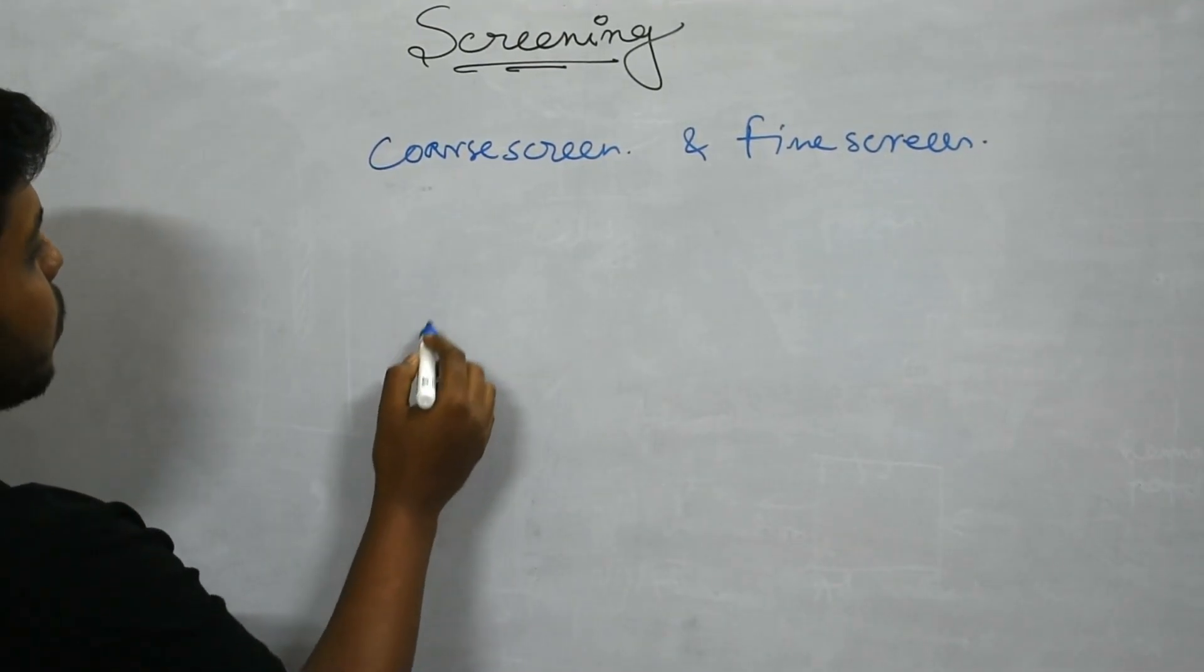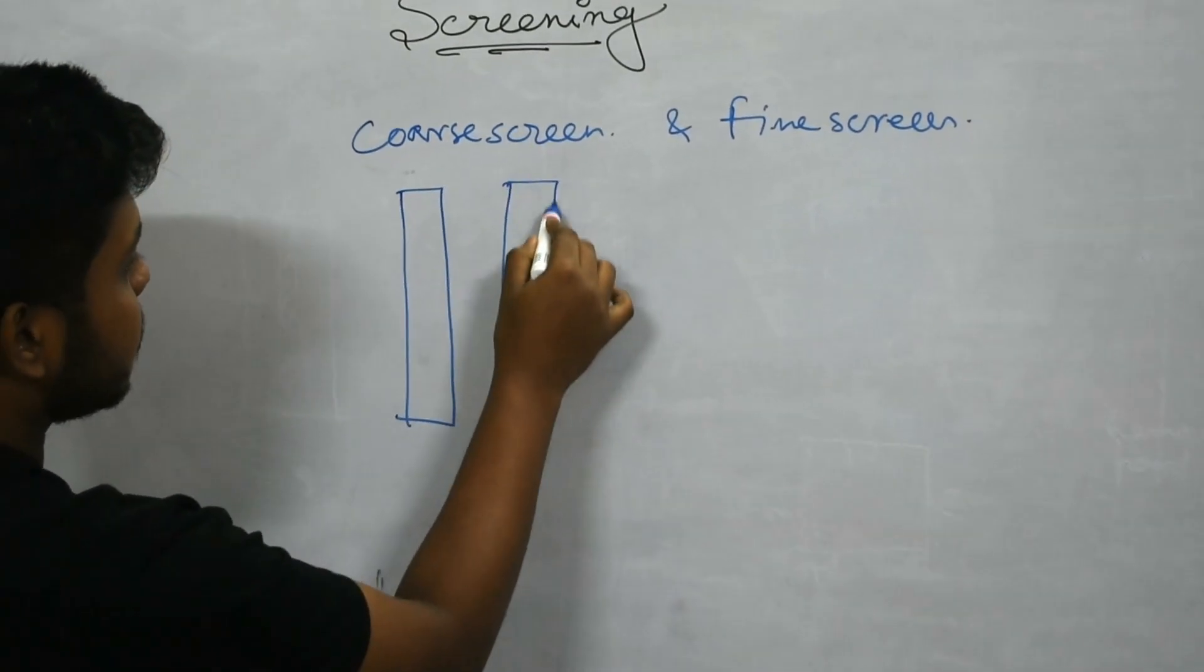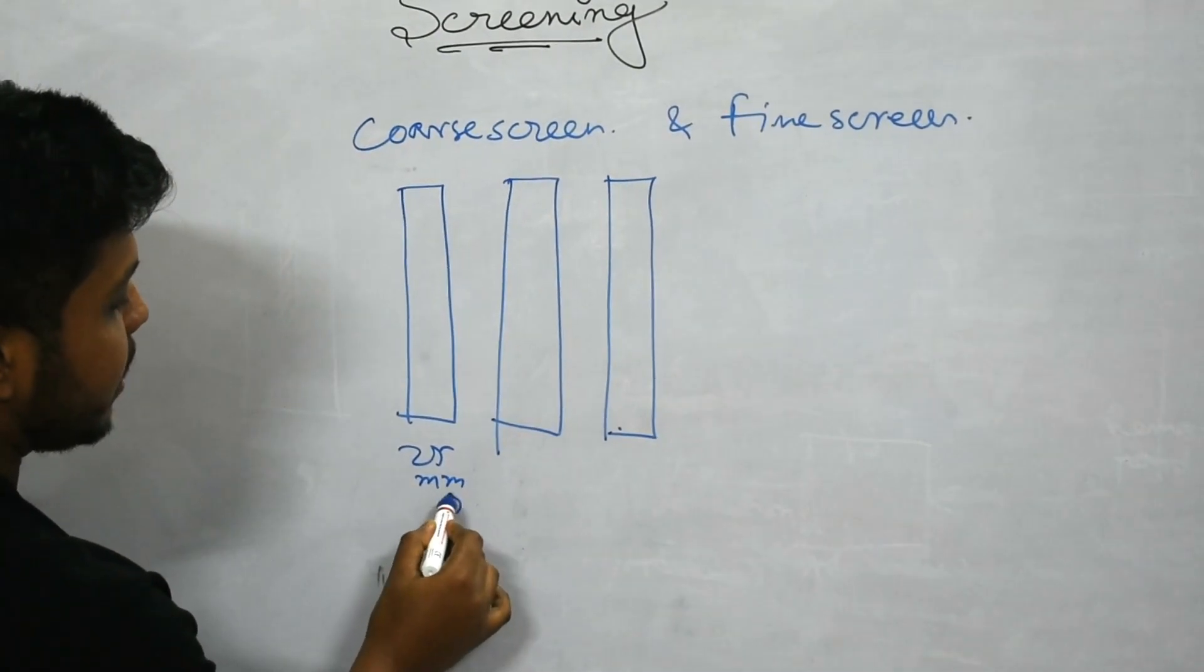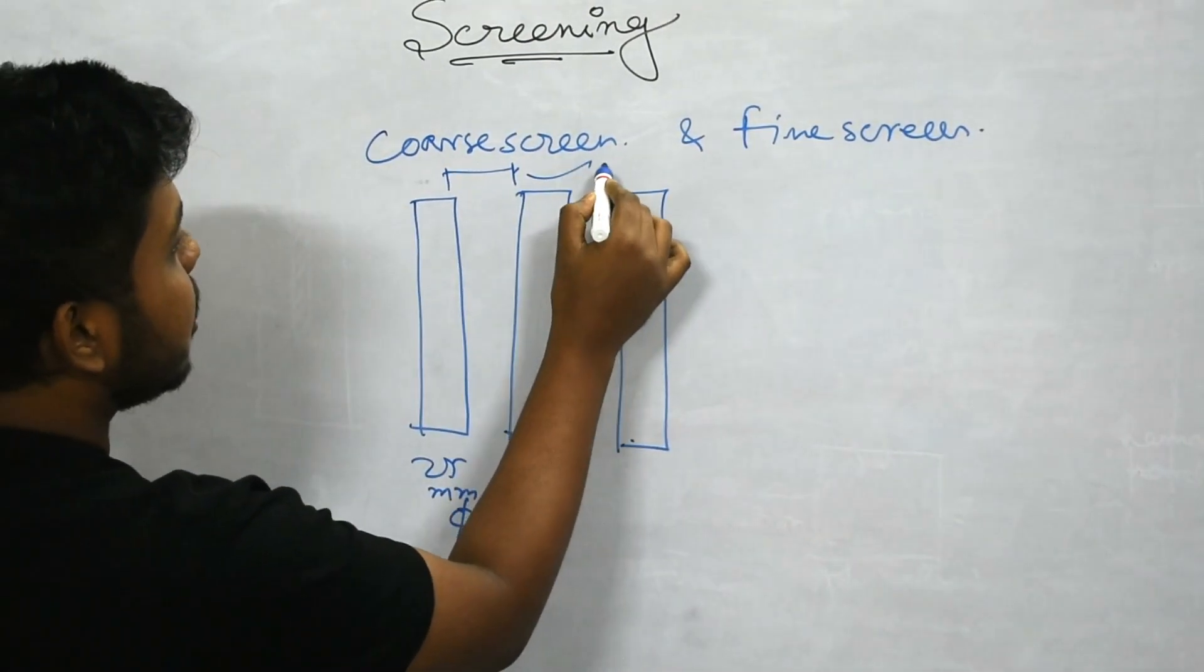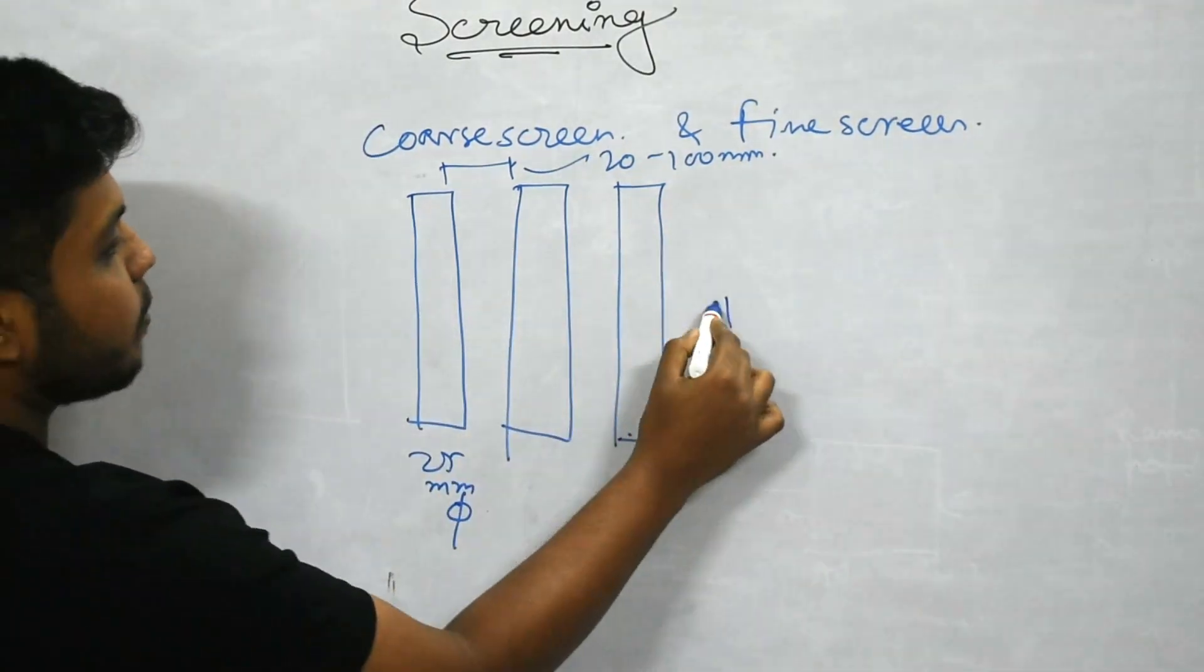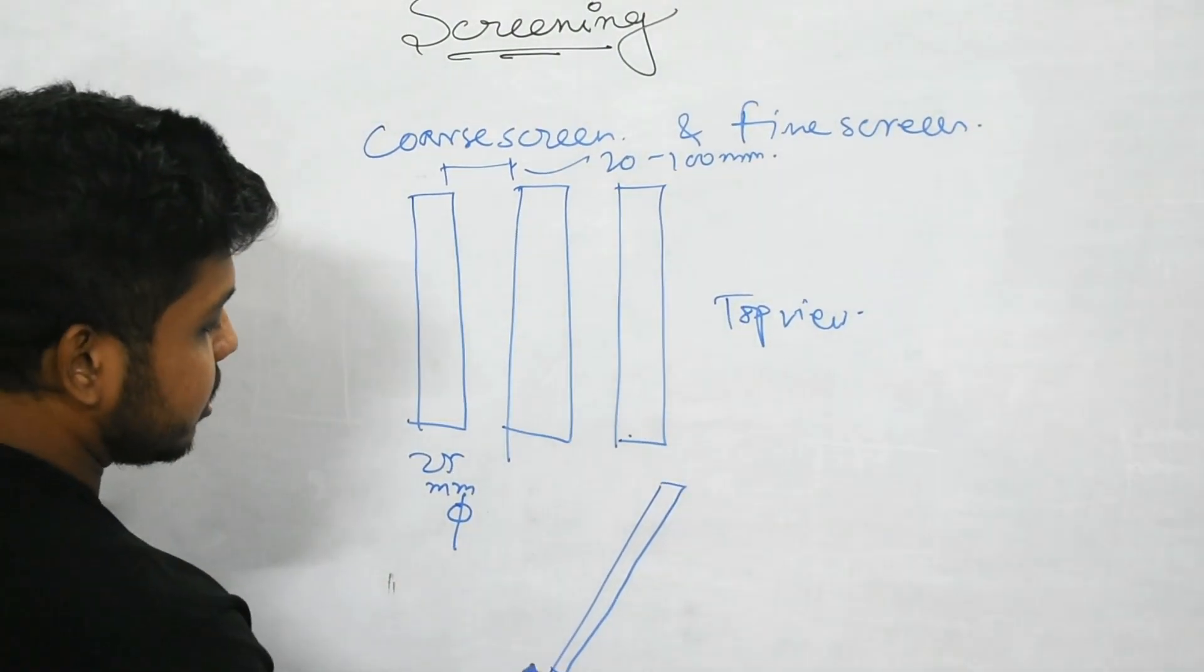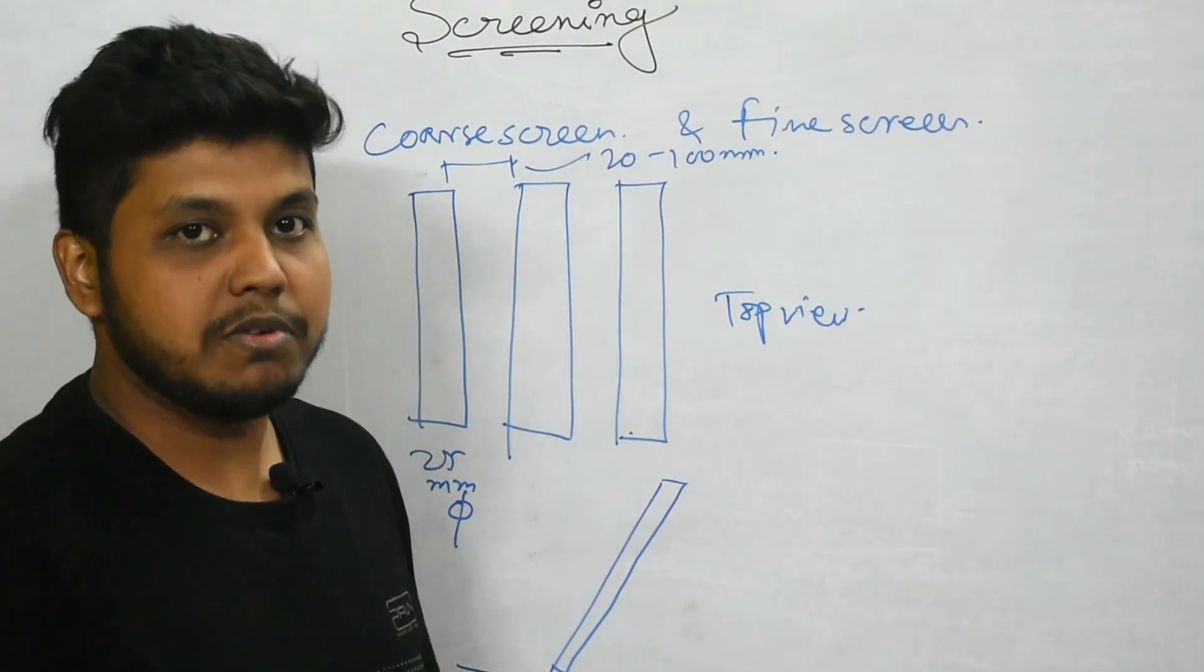What is coarse screen? Coarse screen is some bars provided in parallel. These bars are of 25 mm diameter and these openings are of 20 to 100 mm. This is the top view. These are provided in some inclination because this inclination provides better removal efficiency.